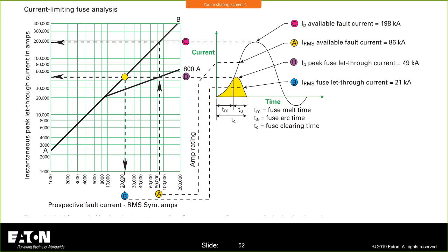So what does this tell me? My AB line tells me what would be let through if my fuse wasn't in the picture, and that is this top point of the peak short circuit current that would flow in my circuit. Because I have the current limiting fuse in the picture, to know what this new peak is, I go up and over. That's called the up-over method. That gets me this peak value.